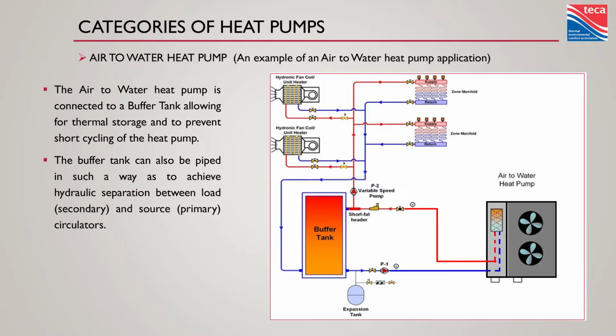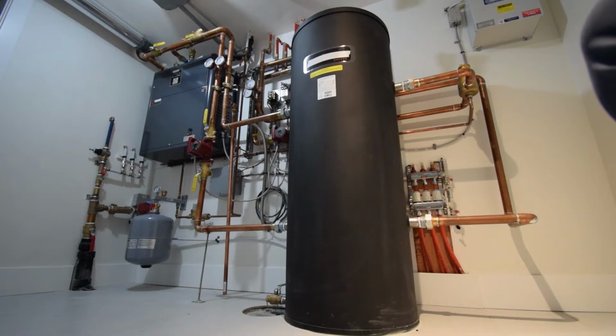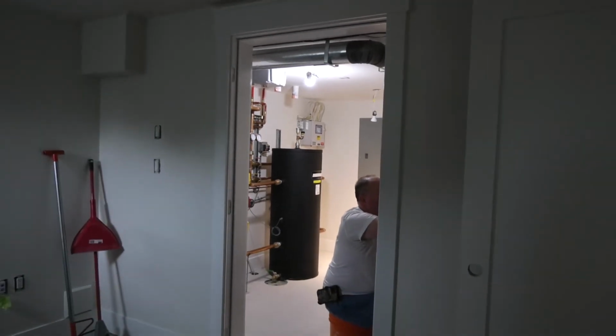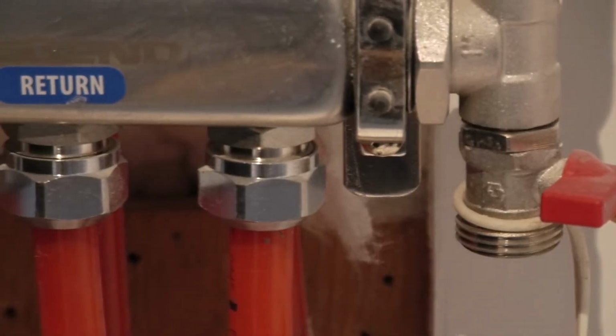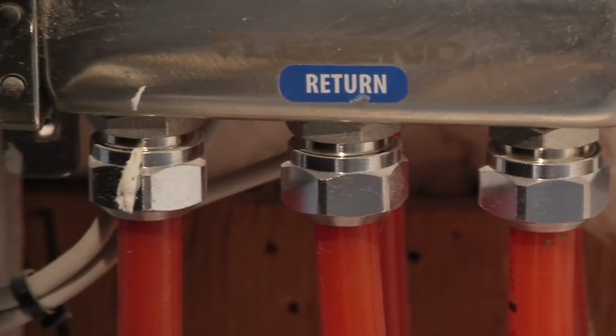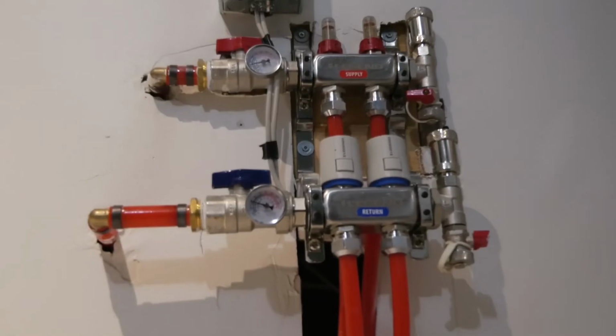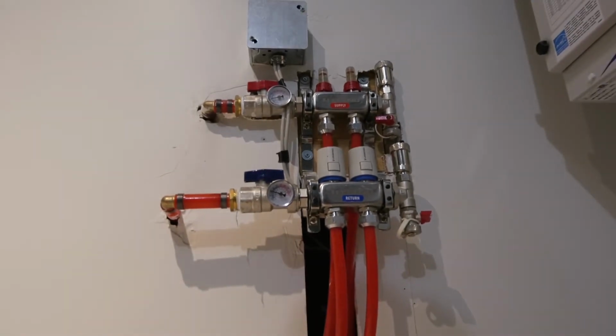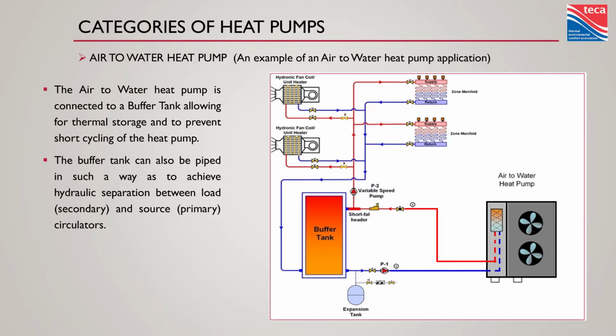The thing about a conveyor belt of heat energy is it's not just putting heat into water. That water has to get rid of that heat somewhere. So you can't just warm up the water. It helps to store it. So think of a buffer tank like a thermal battery. It warms up, heat pump turns off, and that essentially becomes your heat source for the rest of that cycle. So you can now deliver heat to your various different heat emitters from that buffer tank while that heat pump is just taking a break. Then when the buffer tank temperature has dropped by a predefined amount, heat pump comes back on and just warms it back up again. So you get some nice long cycle lengths.